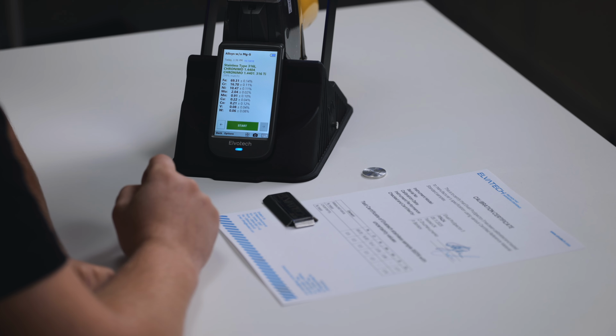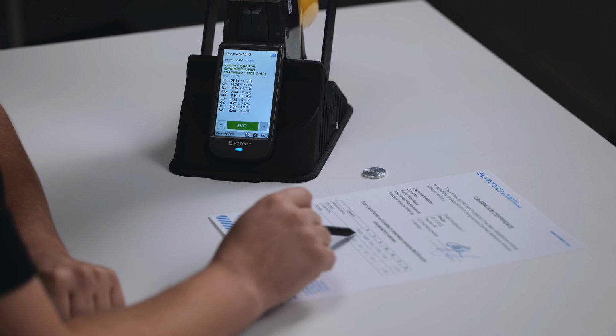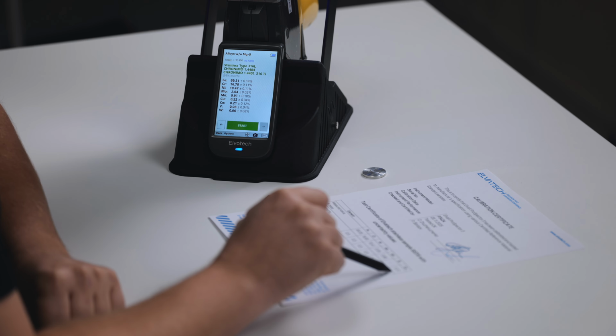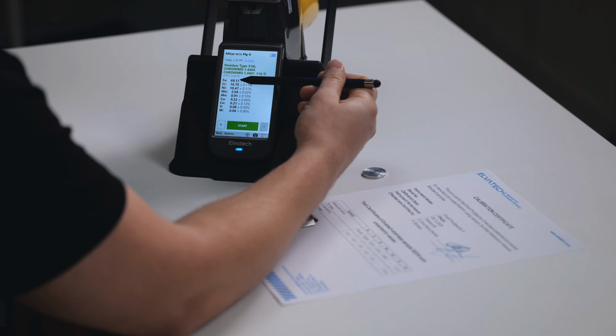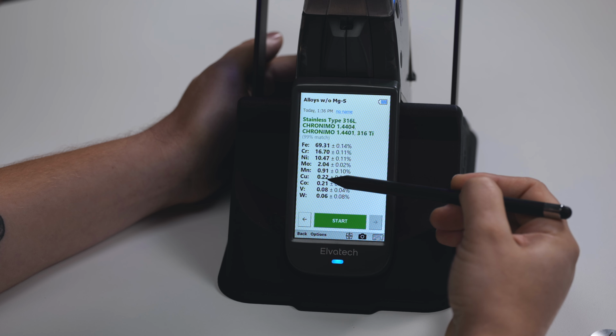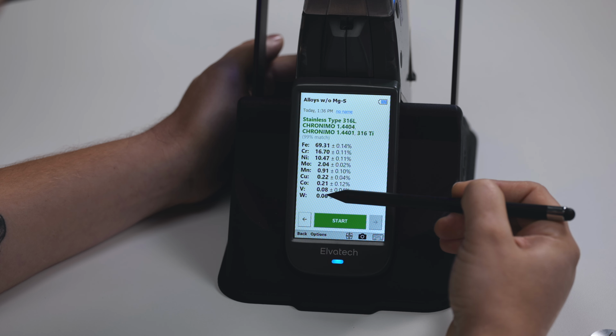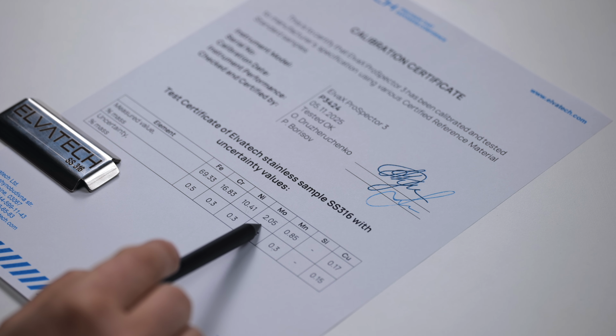So, energy calibration is the way to keep your ProSpector 3 in good shape, so that it correctly recognizes elements and gives stable, reliable results. Periodically measure the 316 stainless steel reference sample and 2024 aluminum alloy if you have the light elements, and compare the values with the certificate, and perform energy calibration only when it is really needed.